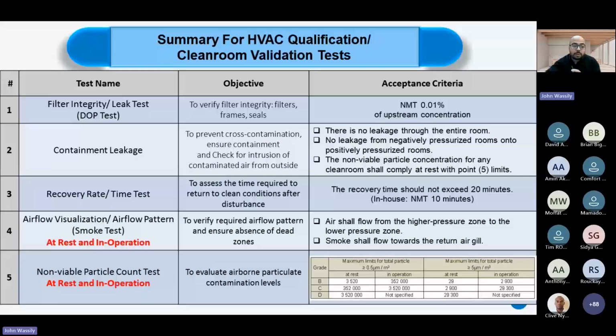Going through the other tests, there is the recovery rate test. This is to make sure that in case of any unintended dirt that has been introduced into the clean room, my HVAC system will be able to recover the initial cleanliness grade within a specific time frame, which is usually not exceeding 20 minutes. So this test is performed by intentionally generating particles inside the clean room and observing the particle count to see how the HVAC system will recuperate and recover the initial cleanliness level.